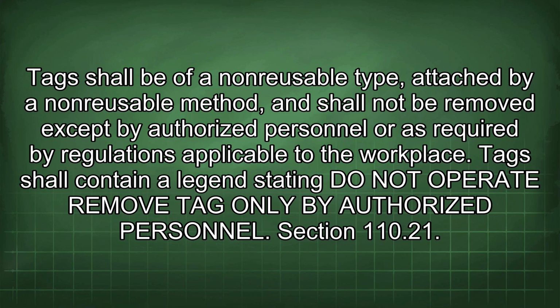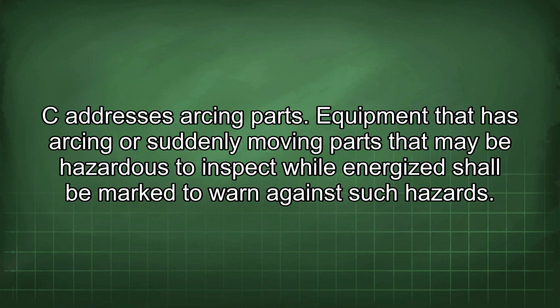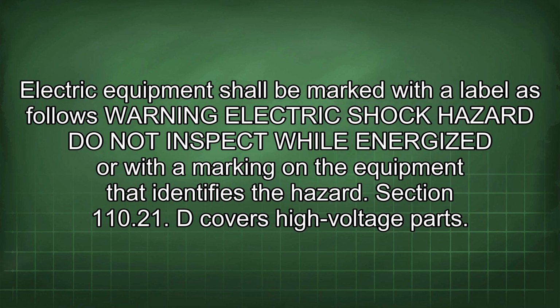Section 110.21(C) addresses arcing parts. Equipment that has arcing or suddenly moving parts that may be hazardous to inspect while energized shall be marked to warn against such hazards. Electric equipment shall be marked with a label as follows: "Warning, electric shock hazard, do not inspect while energized," or with a marking on the equipment that identifies the hazard.